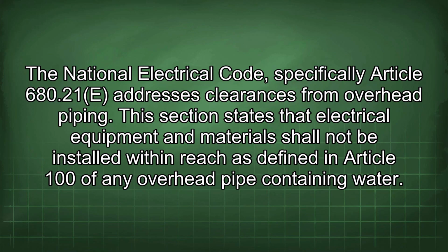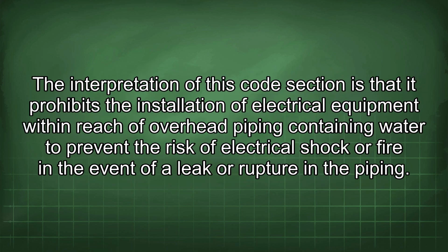The National Electrical Code, specifically Article 680.21(E), addresses clearances from overhead piping. This section states that electrical equipment and material shall not be installed within reach, as defined in Article 100, of any overhead pipe containing water.